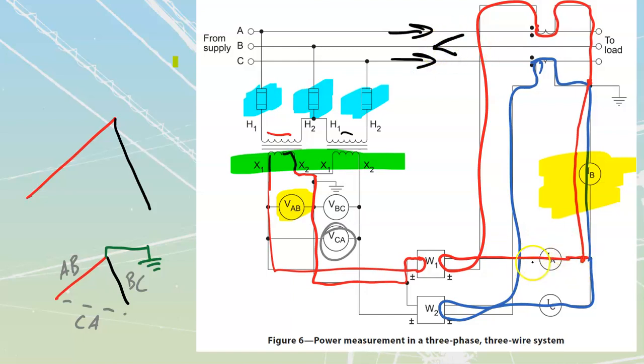So we'd be able to read that with the A and the C, and we'd get the same amount of current coming out through B. It's going to be the sum of those two currents. This will always work out, and you just need to recognize that we've got two separate currents, split them, measure them individually, then combine both currents back together, run them through another ammeter that combines them, and back out to the load.